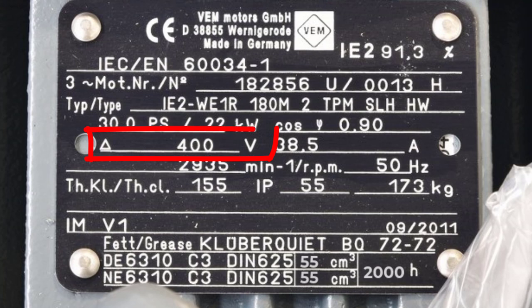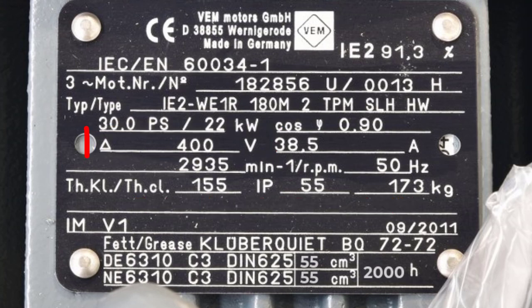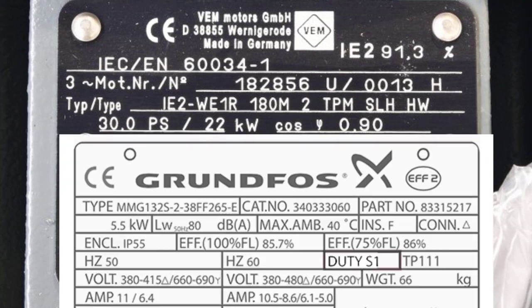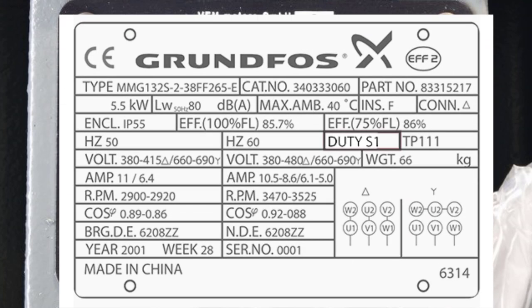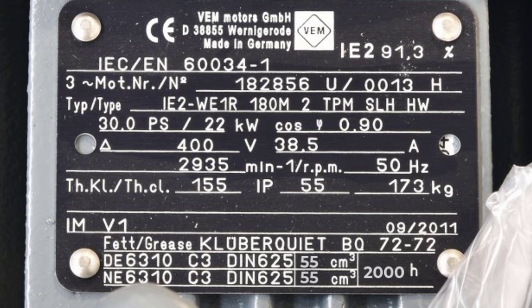The rated line-to-line voltage is 400 volts plus or minus 10%, and the motor must be connected in delta configuration. Be careful with motor voltage and connection relationships — for example, you should only connect the motor at a given voltage input in star connection. Attempting delta connection in the wrong configuration can cause harmful effects on the motor's insulation.